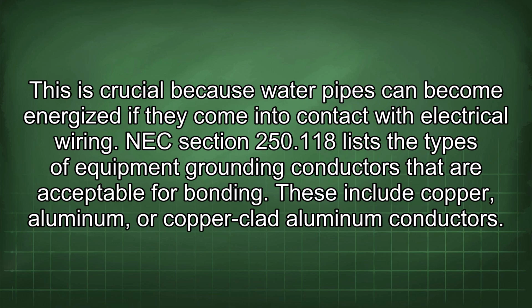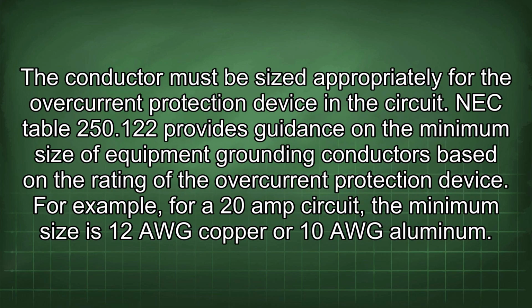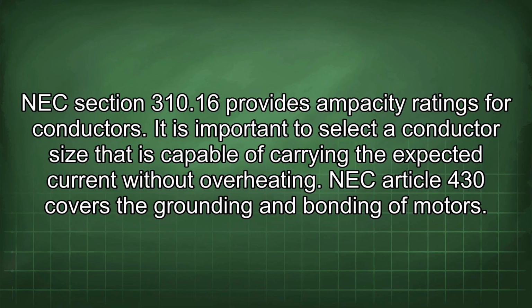NEC Section 250.118 lists the types of equipment grounding conductors that are acceptable for bonding. These include copper, aluminum, or copper-clad aluminum conductors. The conductor must be sized appropriately for the overcurrent protection device in the circuit. NEC Table 250.122 provides guidance on the minimum size of equipment grounding conductors based on the rating of the overcurrent protection device. For example, for a 20 amp circuit, the minimum size is 12 AWG copper or 10 AWG aluminum. NEC Section 310.16 provides ampacity ratings for conductors. It is important to select a conductor size that is capable of carrying the expected current without overheating.